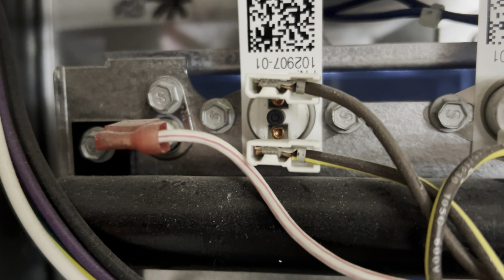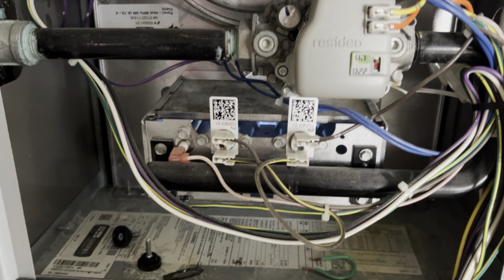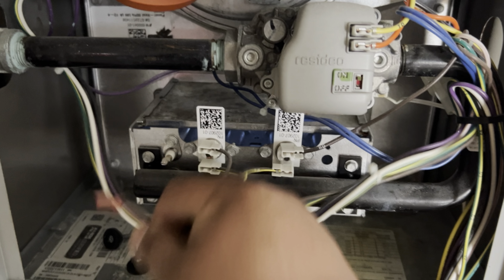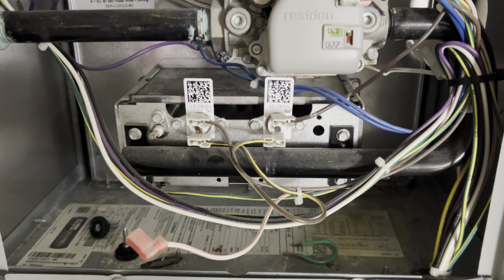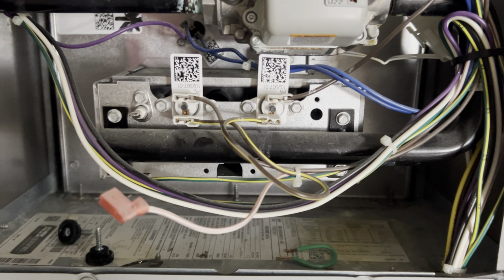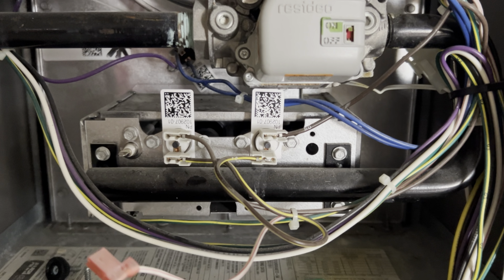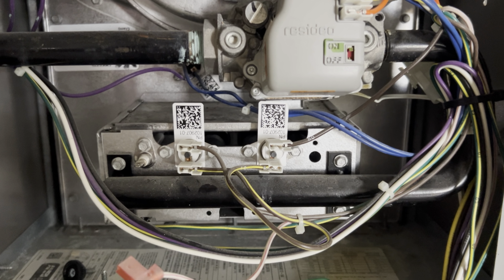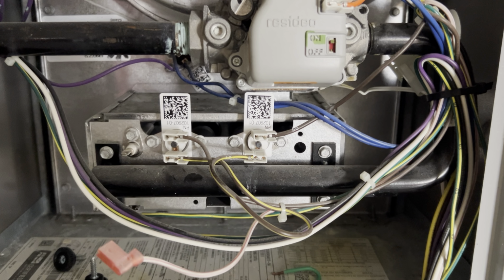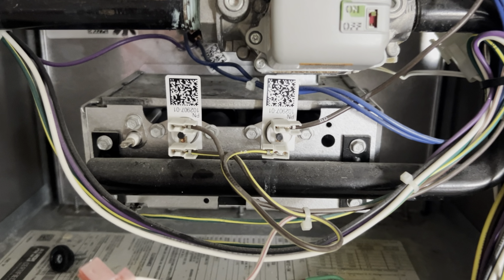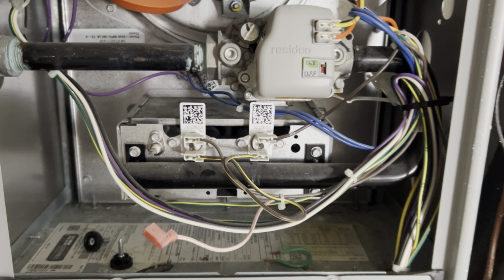If the flame rolls out of the unit, there are these rollout switches that need to be manually reset by pressing that black button in the middle. That protects the system from overheating. By removing this wire, I am simulating a bad or a worn flame rod. The flame rod needs to be checked periodically if the flame does go out. It can be removed by taking off this top screw here. It's a 1/4 inch screw, and the sensor can be cleaned using sandpaper.